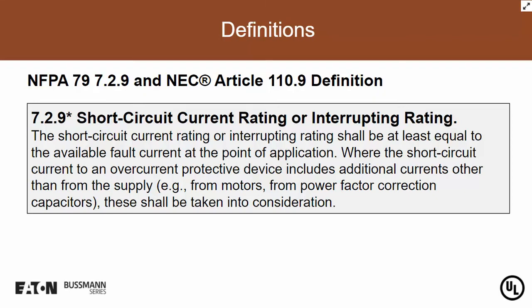You can see in 7.2.9, we go on to read where the short circuit current to an overcurrent protective device includes additional currents, say, for example, other than from the supply. So, for example, from motors where you have a collapsing magnetic field, or maybe from power factor correction capacitors where you have the energy stored in the capacitors. Under short circuit currents, those factors can be considered as well.